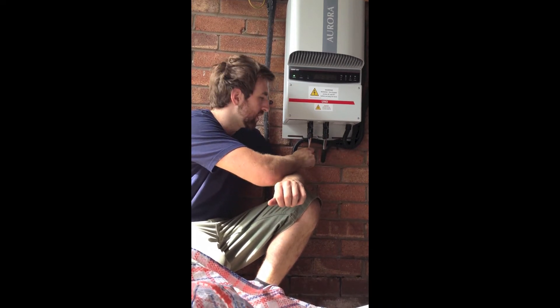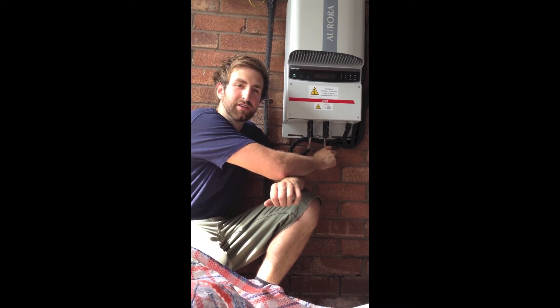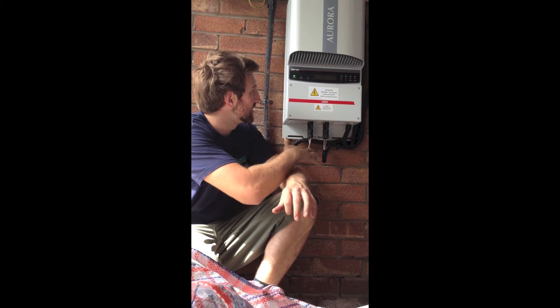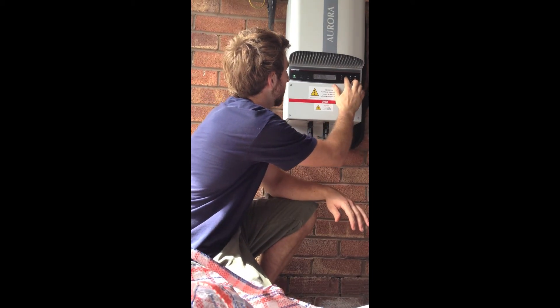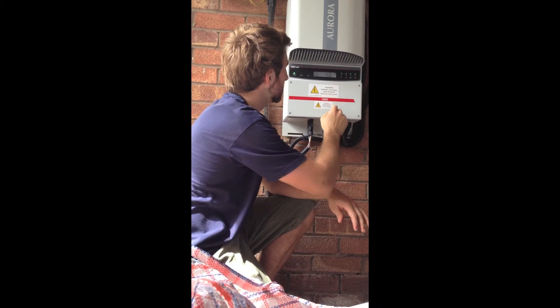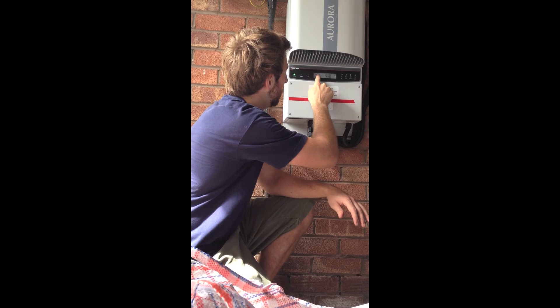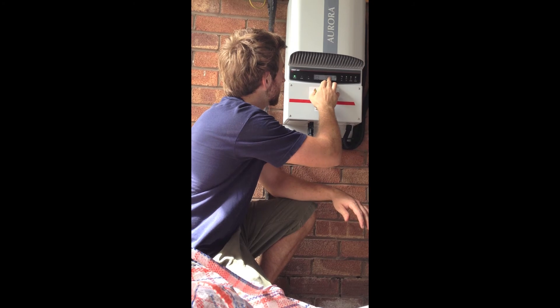This one facing west with 10 solar panels on it, and this circuit facing east with 6 solar panels on it. The benefit of this is the end user can go into the solar PV inverter and see the live output of each individual circuit. String 1 is generating 1.4kW, 1.5kW at this moment in time.